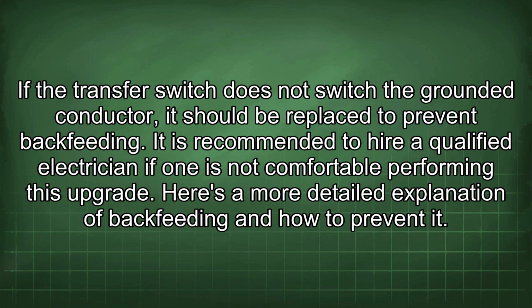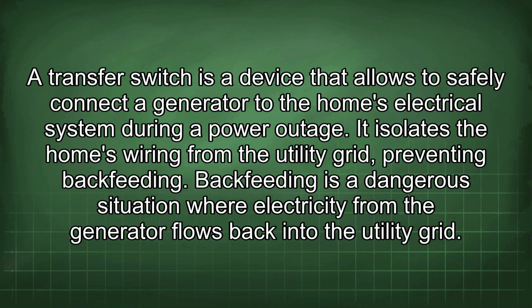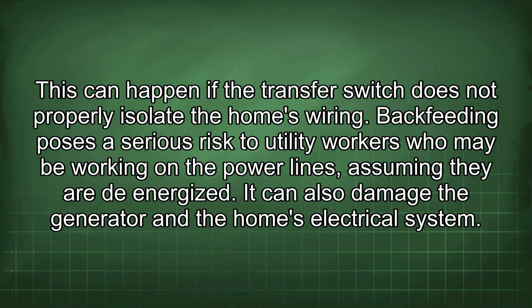Here's a more detailed explanation of backfeeding and how to prevent it. A transfer switch is a device that allows one to safely connect a generator to the home's electrical system during a power outage. It isolates the home's wiring from the utility grid, preventing backfeeding. Backfeeding is a dangerous situation where electricity from the generator flows back into the utility grid. This can happen if the transfer switch does not properly isolate the home's wiring. Backfeeding poses a serious risk to utility workers who may be working on the power lines, assuming they are de-energized. It could also damage the generator and the home's electrical system.